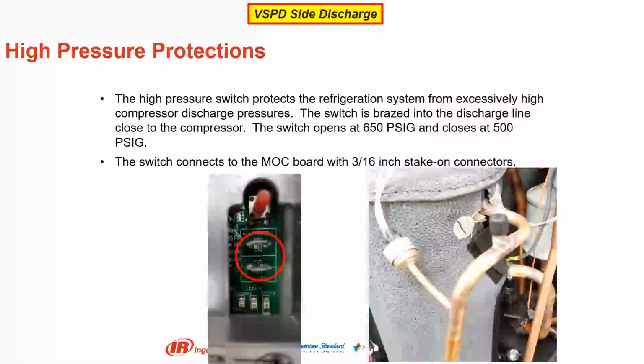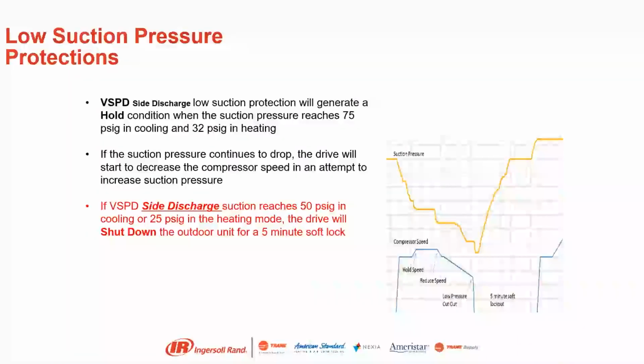High pressure protections are going to land right there on the MOC board. Low suction pressure cuts out at 32 PSI in heating. If variable speed discharge suction reaches 50 PSI in cooling or 25 PSI in the heating mode, the drive will shut down the outdoor unit. So that's critical. We got to verify if our low suction pressure transducer is reading correctly, because we'll get these lockouts.